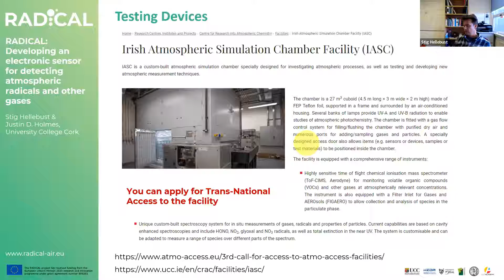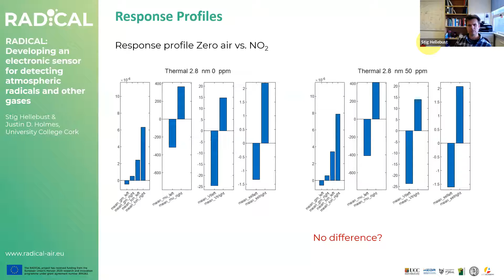So that would be the third stage of the testing. And of course, the final stage of the testing will be the real atmosphere. And for that, we'll use our atmospheric monitoring station, the air quality monitoring station in Cork. So we've done some tests, and you get a profile of measurements, and then you want to see, can you see any difference? Is there any difference now? Here on the left, I have zero air. On the right, I have 50 ppm of NO2. And then the question is, can you tell from the measurements that there is a difference in concentration of NO2?